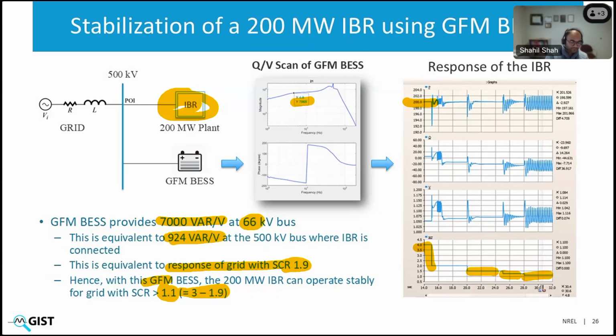Now, when we use Q by V scans or P by theta scans to size a grid forming resource, it is a slightly approximated approach because we are ignoring coupling between the active and reactive power. Somehow for this IBR, the analysis turned out to be exact, that it indeed becomes unstable only at SCR of 1.1. That is because for this IBR plant, the coupling between the active power and reactive power axes was quite negligible. So we have to build some level of conservatism into this type of sizing, because we are doing this without using the exact models.